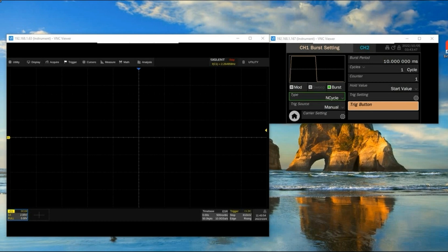There is a video already on sequence mode directly, so I'm not going to go into gory detail about that. But I would like to let you know that there's a really easy way to set a number of frames. Once that number of trigger events has been captured, the instrument will automatically go into stop. I'd like to quickly go through that.